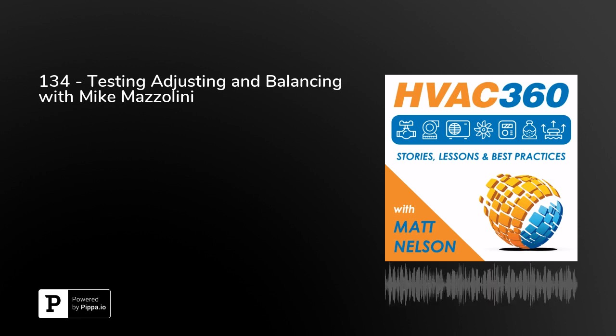is, let's just call it a small ducted return system. When you look at the unit total and the minimum outside air required, and then you look at the return total, and the return total matches the supply fan total, I always write in our reports, let's say it's two inlets, okay, 2 inlets at 100 CFM, and it requires 100 CFM outside air. So we've got 300 CFM total that we're working with.